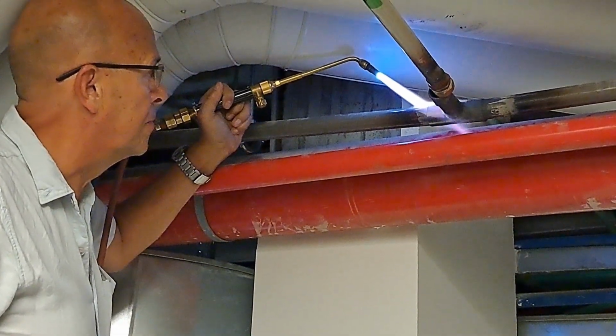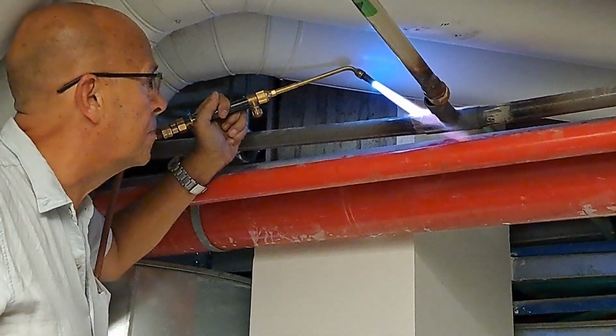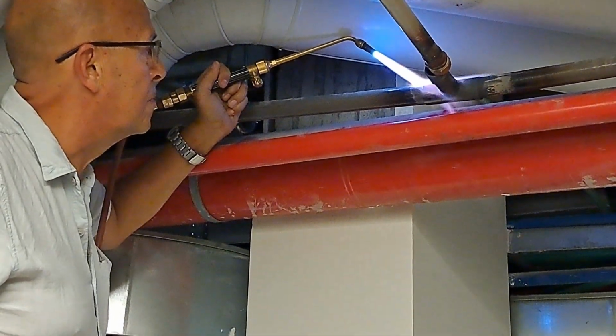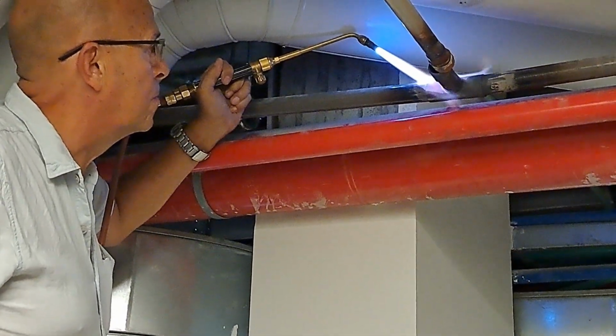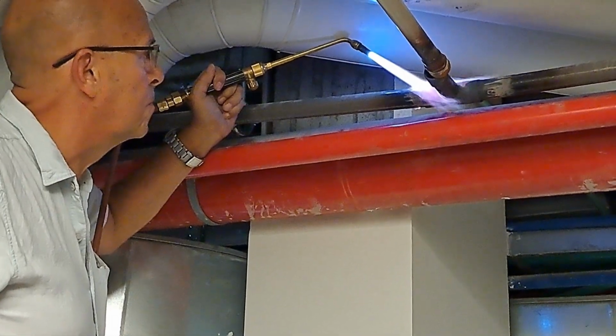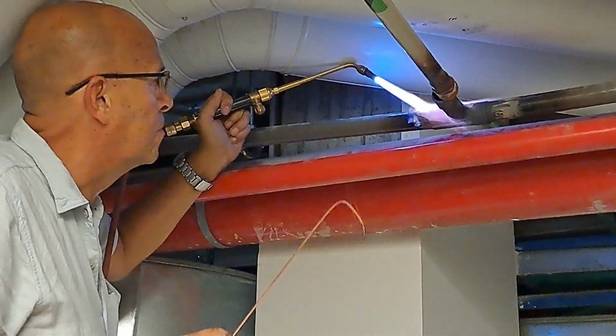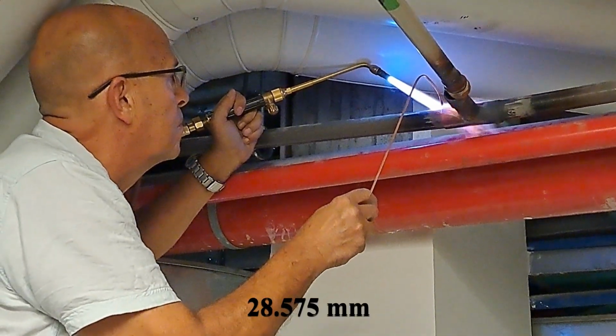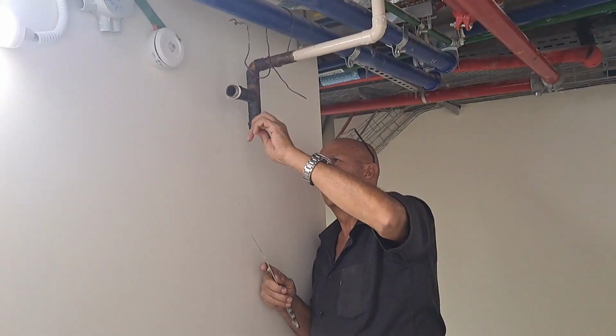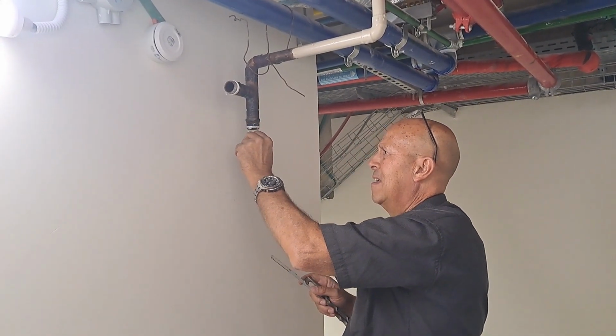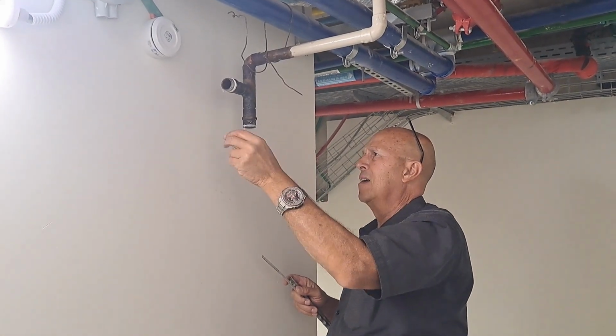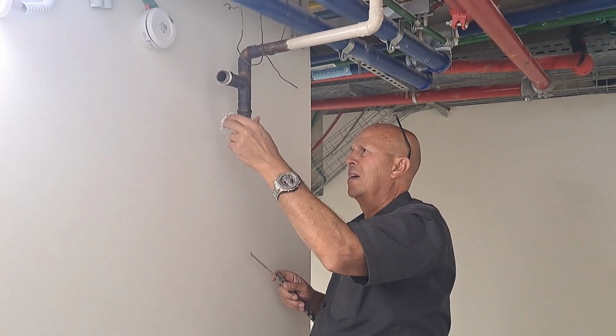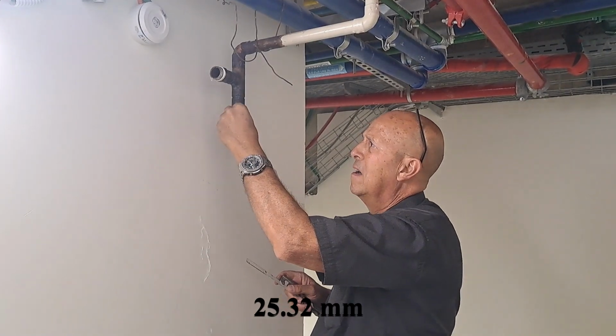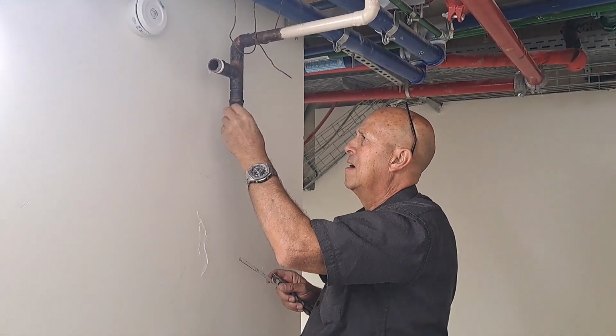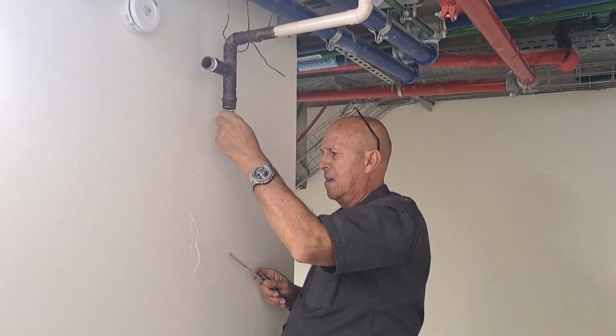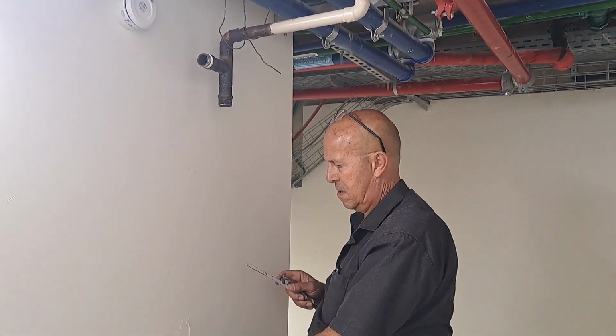The installation of the pipework and connection to the existing line was carried out by Bachuri Building Limited under the management of Itsik Cohen. He installed the system, connecting it to the existing line. He used 1 1/8 inch copper piping and helium-rated ball valves. And yes, we use inches to measure pipe diameters even in Israel. The inner diameter of this piping is nominally 0.997 inch. The piping was welded and the ball valves and gas meter connected with Teflon tape.